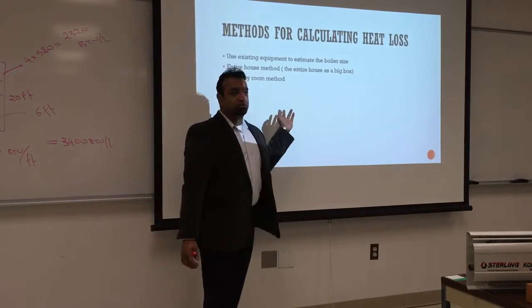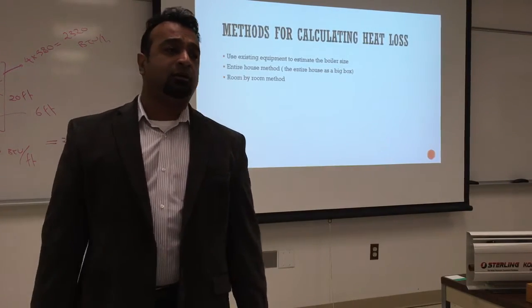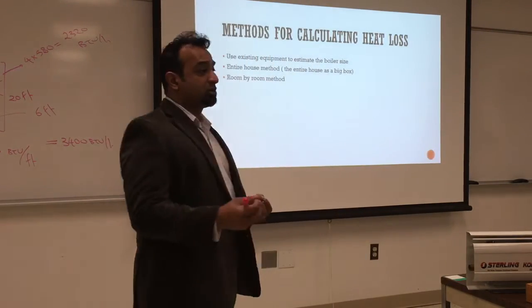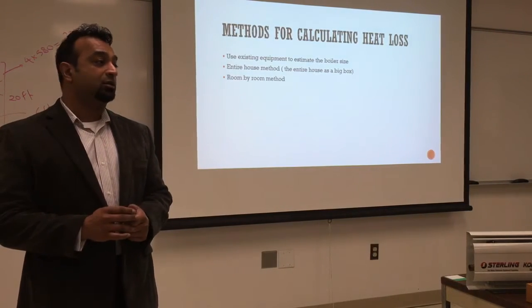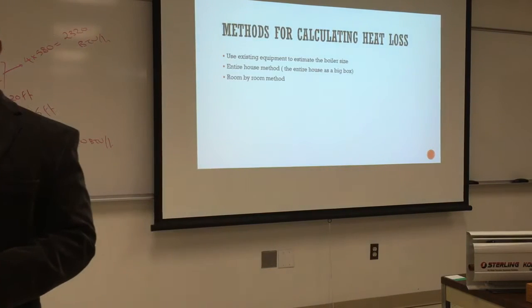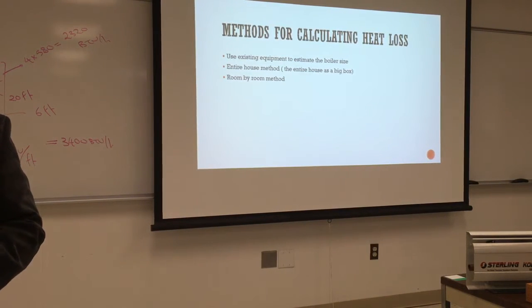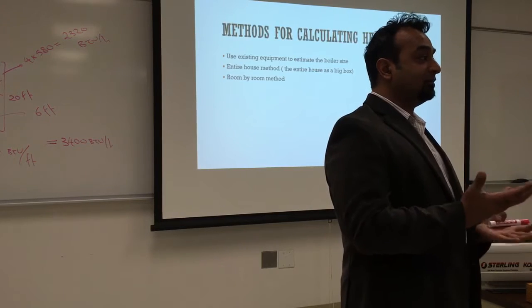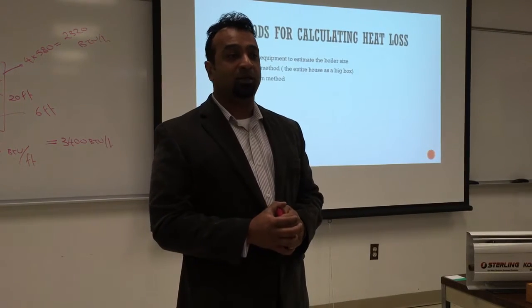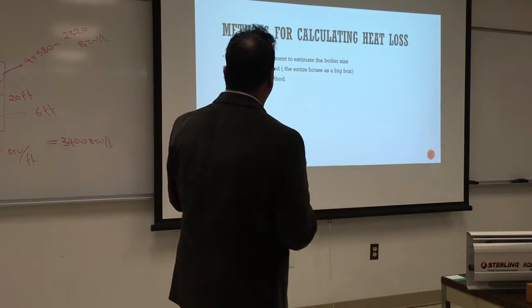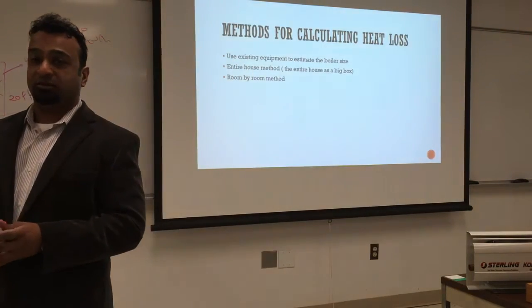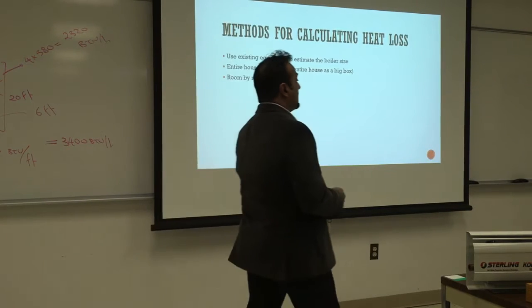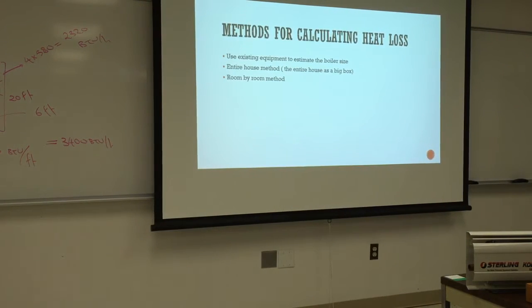The room-by-room method is the most recommended by ASHRAE. It gives you better heat load calculation and better sizing for each room, telling you how many BTUs each room needs so you don't overheat or underheat it. Nothing is more annoying than walking into a house with different temperatures—the kitchen very hot, the room cold, the living room drafty. Uneven temperatures are uncomfortable and make the system overwork. The room-by-room method is what we did last semester, and it gives the best results.